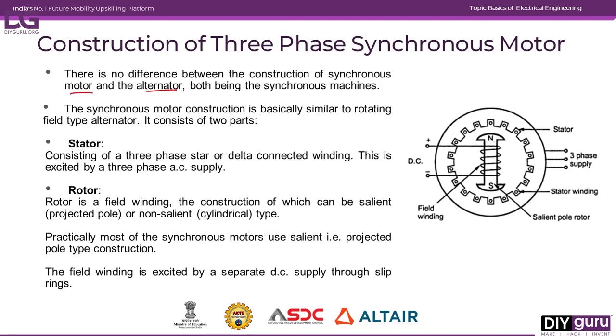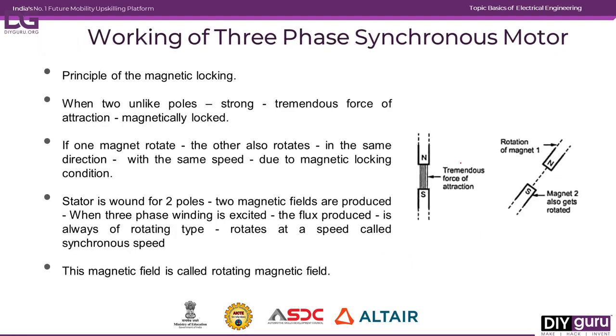There is no difference in construction between the alternator and the synchronous motor; both are synchronous machines. It mainly consists of two parts: the stator and the rotor. The stator is the stationary part and carries the three-phase supply, connected either in star or delta. The rotor is the field winding — the poles may be salient (projected) or cylindrical type; mostly salient pole types are used. The rotor is excited by a separately excited DC supply through slip rings.